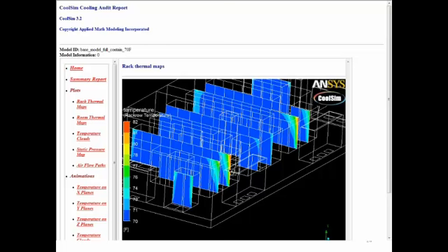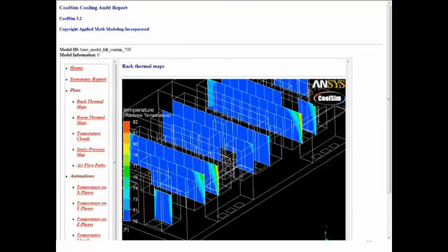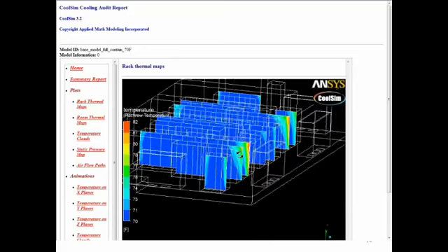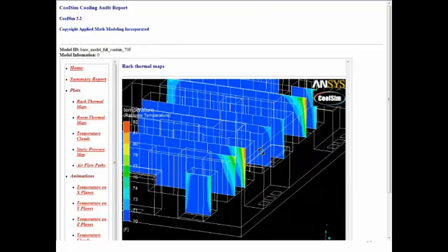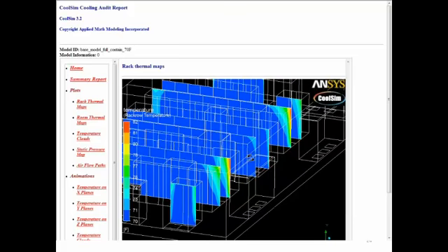That's probably not going to bother a server. And furthermore, it's at the top. So what you would do there is just keep your servers away from the top. Yeah, or just place equipment there that's not going to have high demands. That's correct. Again, these tools are guides. They're not meant to be an absolute indicator of what's going on.